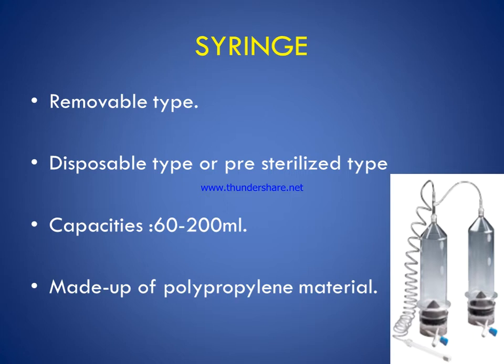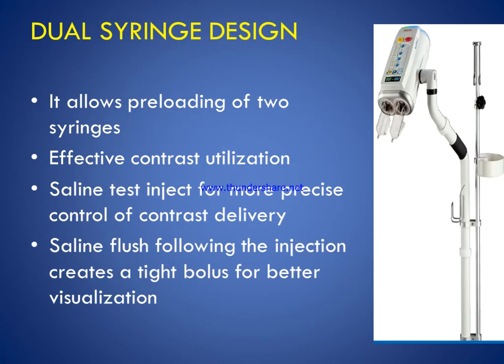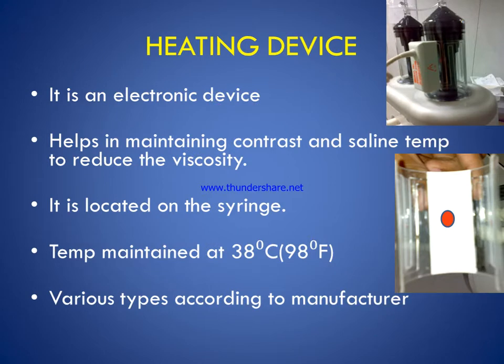The syringe capacity ranges from 60 to 200 ml and is made of polypropylene. There are dual syringe designs which allow pre-loading of two syringes, helping in effective contrast utilization. The saline test injection allows more precise control of contrast delivery, and saline flushing following the injection creates a tight bolus for better visualization.